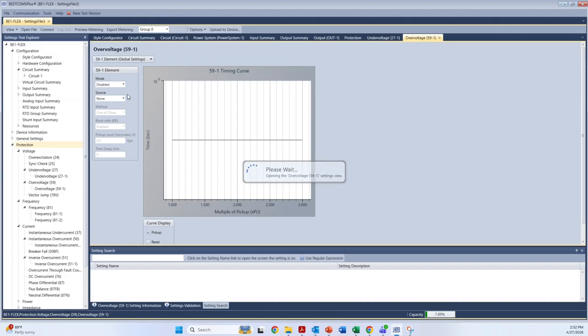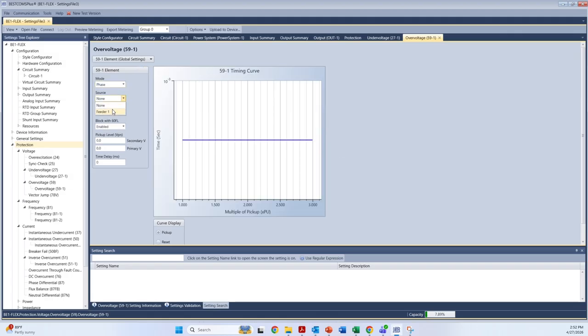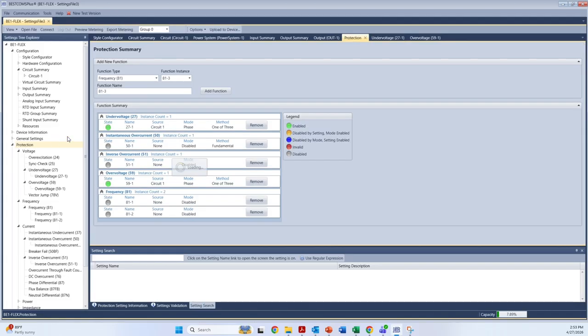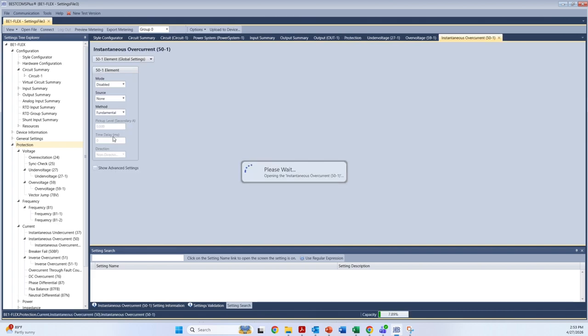We'll do the 59 next. Again, we'll select phase for the mode. Select feeder 1, 1 of 3, and put in the pickup level and a time delay. Similar for the time overcurrent.